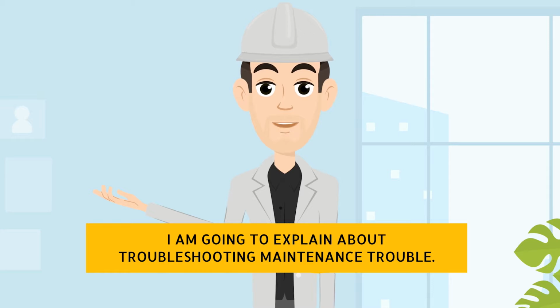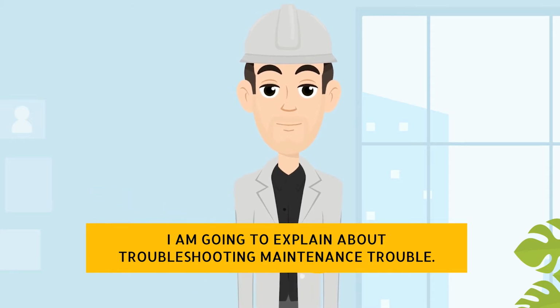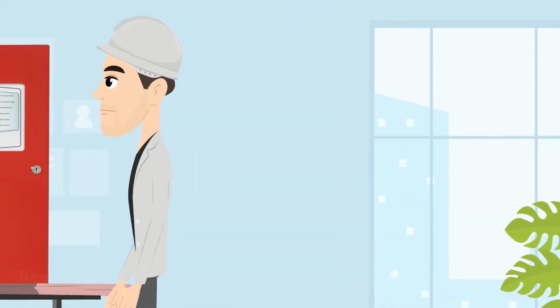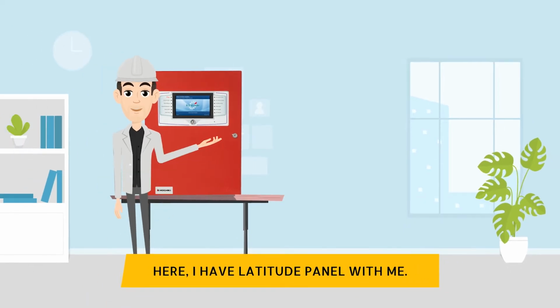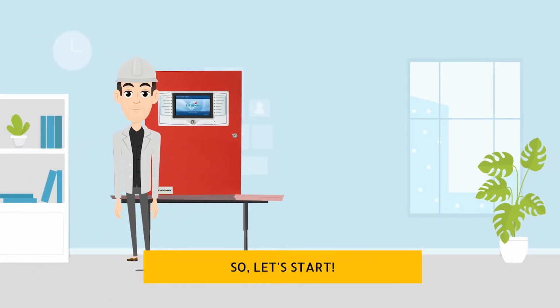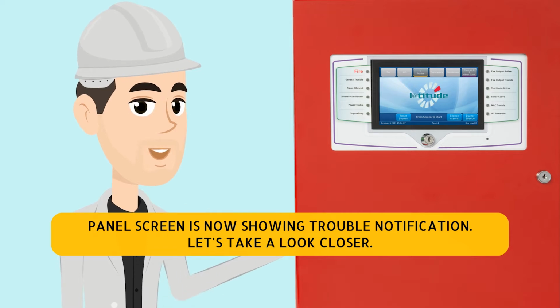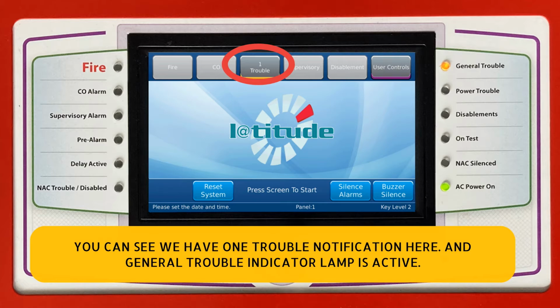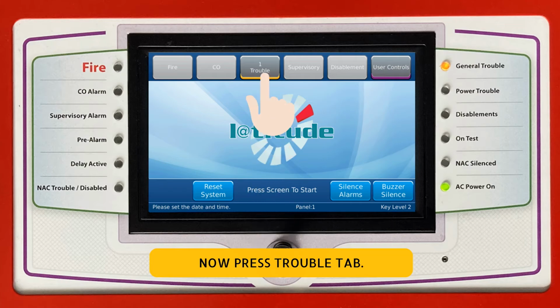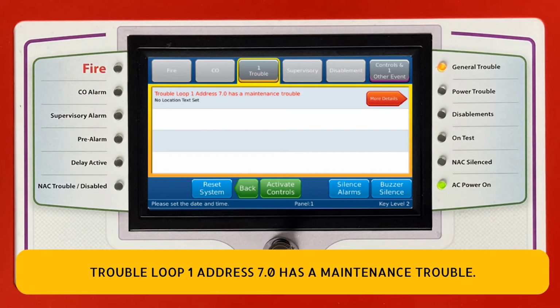I am going to explain about troubleshooting maintenance trouble. Here, I have Latitude panel with me. So, let's start. Panel screen is now showing trouble notification. Let's take a look closer. You can see we have one trouble notification here, and general trouble indicator lamp is active. Now press Trouble tab. Trouble loop 1 address 7.0 has a maintenance trouble.